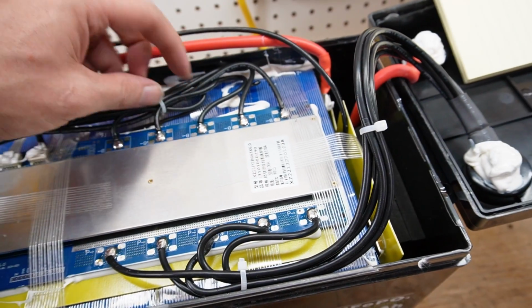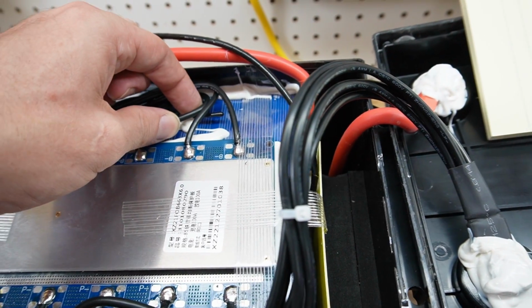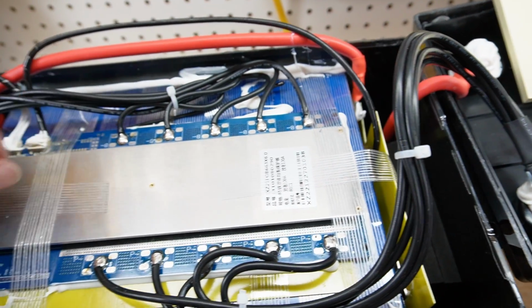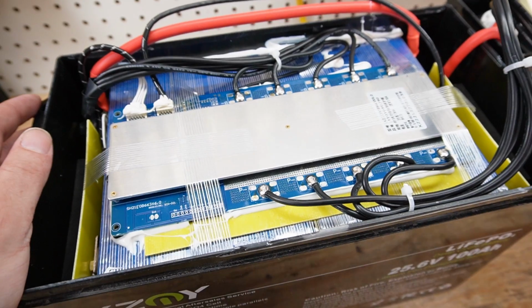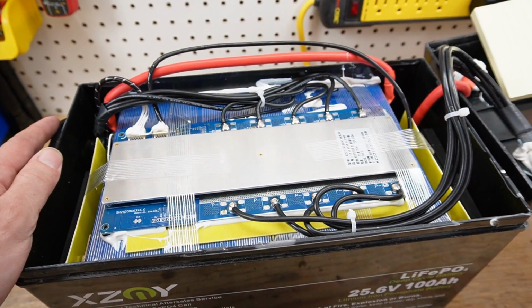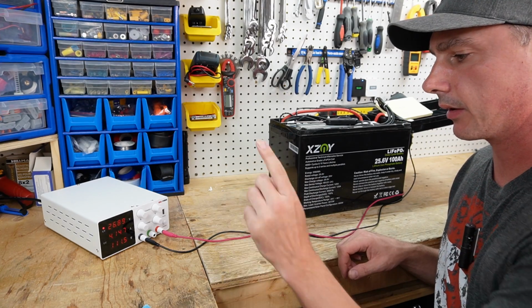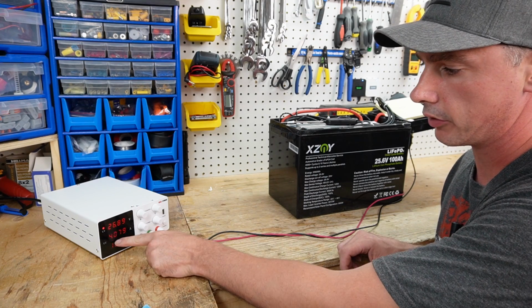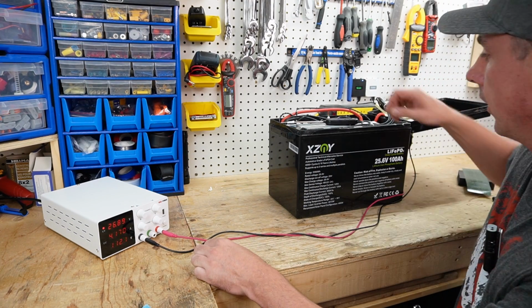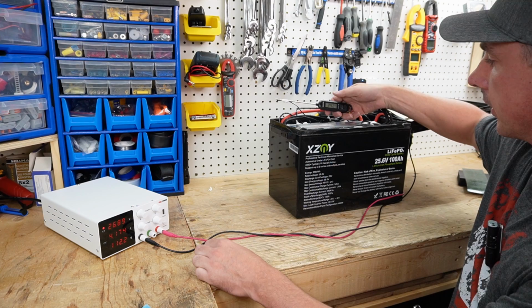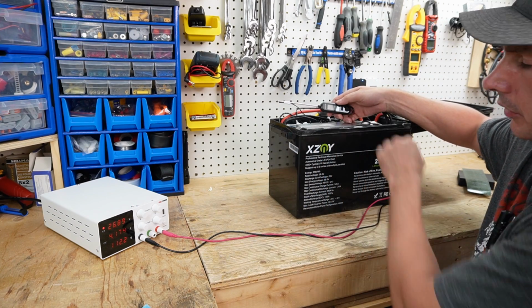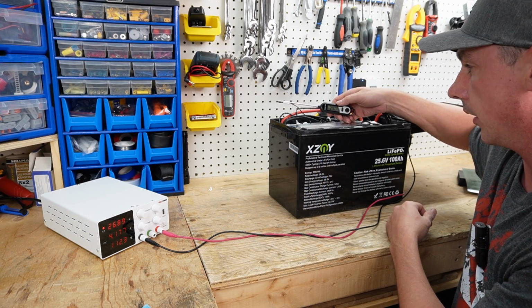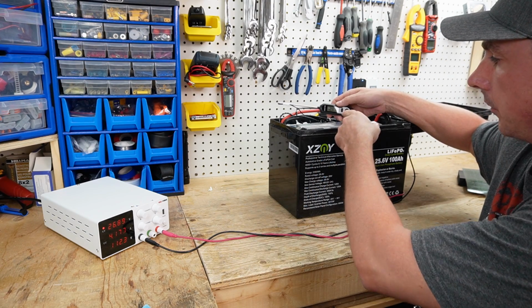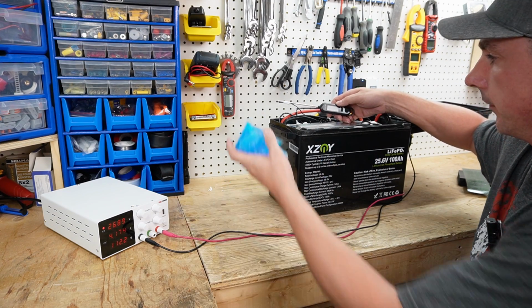Let's test - we do have a temperature sensor here, so let's pull that out and test it for cold temperature and overheat protection. Okay, cold temperature protection test. I have my bench power supply charging with roughly 4 amps. Now I'm going to try and do this here. I was just touching the probe, so it's showing 29.1 degrees. It will cool down if I give it time, but I want to do this test.